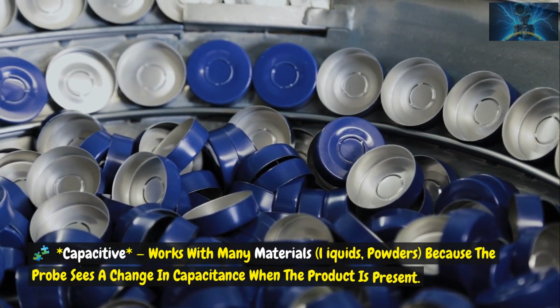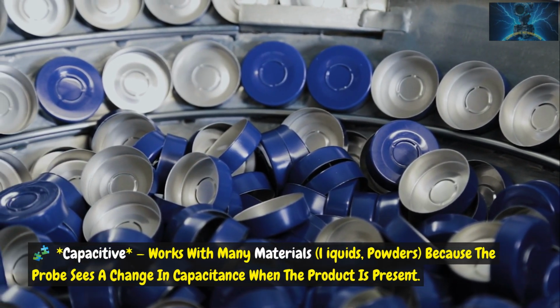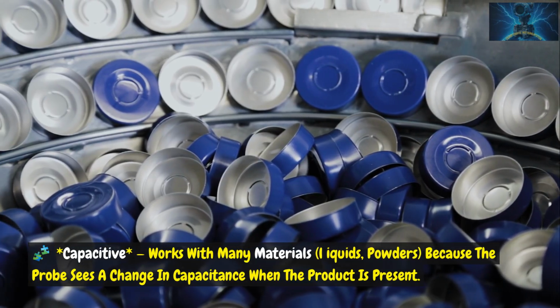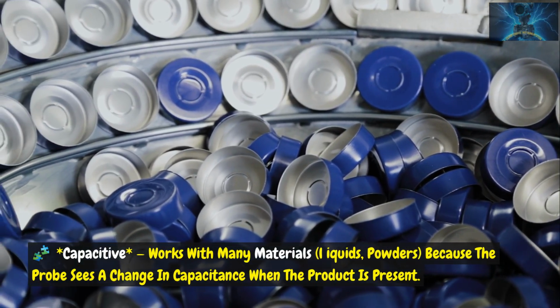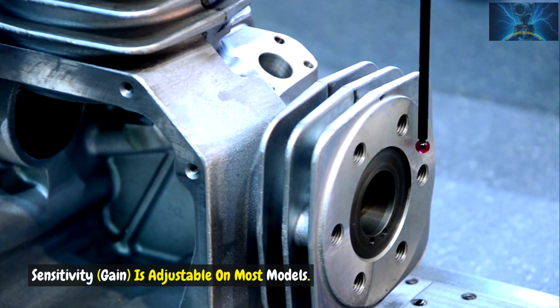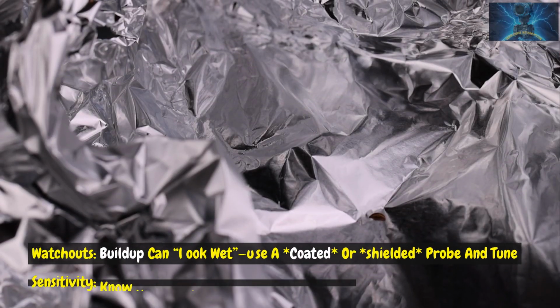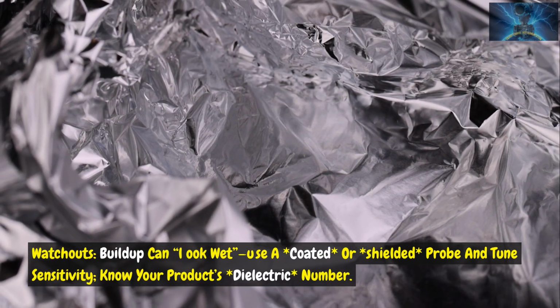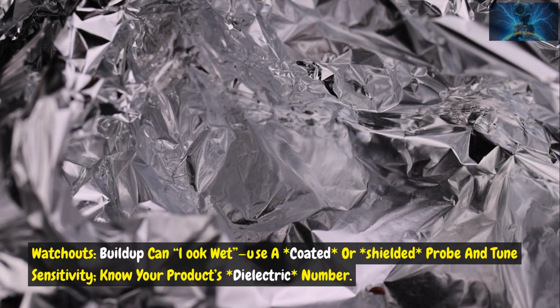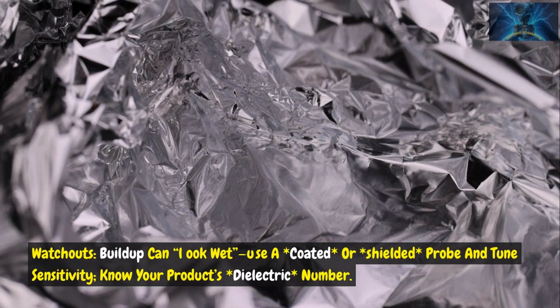Capacitive: works with many materials, liquids, and powders, because the probe sees a change in capacitance when the product is present. Sensitivity gain is adjustable on most models. Watchouts: buildup can look wet. Use a coated or shielded probe and tune sensitivity. Know your product's dielectric number.